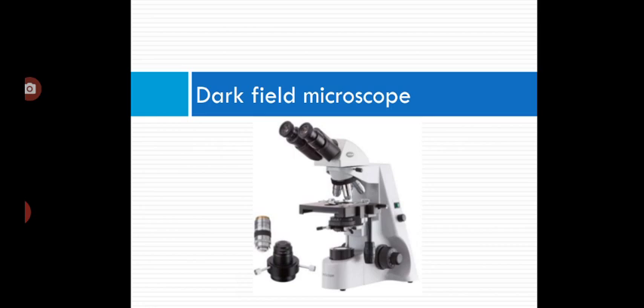The result is a cone of light where rays are diffracted, reflected, and/or refracted off the object, ultimately allowing the individual to view a specimen in dark field. The dark field condenser with a central circular stop, which illuminates the object with a cone of light, is the most essential part of this dark ground microscope.